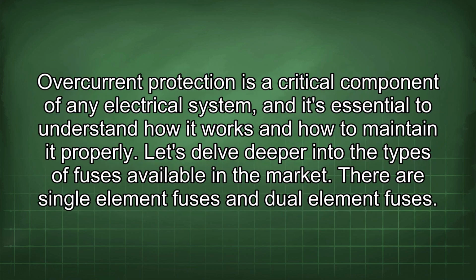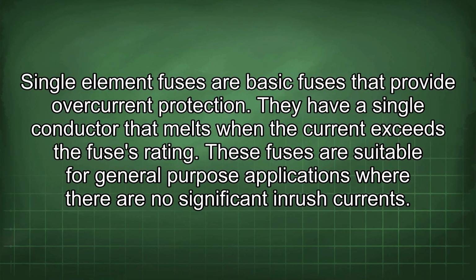Overcurrent protection is a critical component of any electrical system, and it's essential to understand how it works and how to maintain it properly. Let's delve deeper into the types of fuses available in the market. There are single-element fuses and dual-element fuses. Single-element fuses are basic fuses that provide overcurrent protection. They have a single conductor that melts when the current exceeds the fuse's rating. These fuses are suitable for general-purpose applications where there are no significant inrush currents.